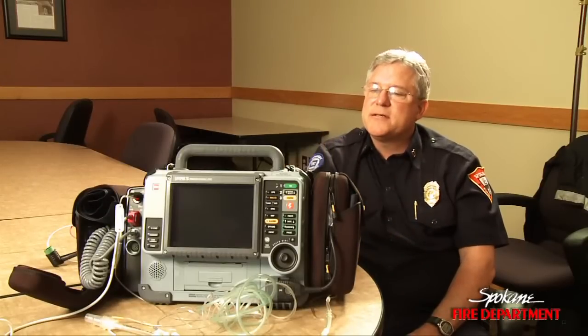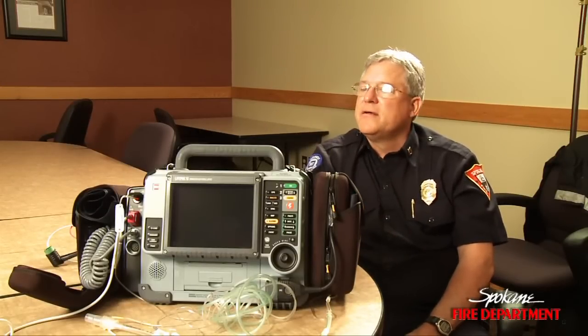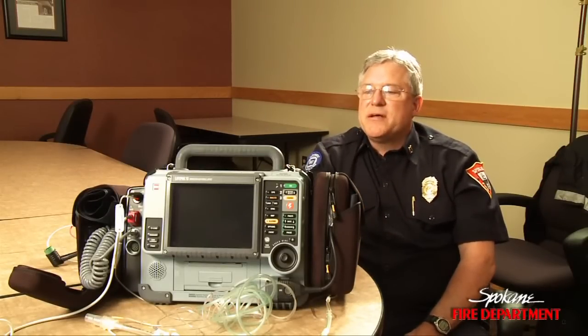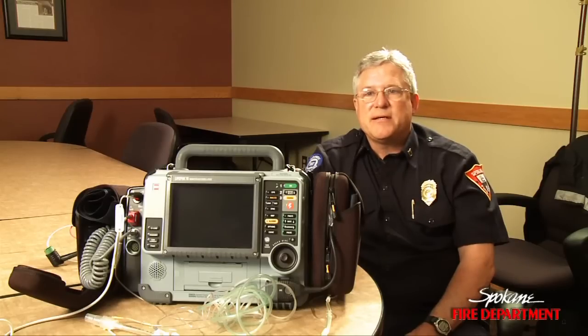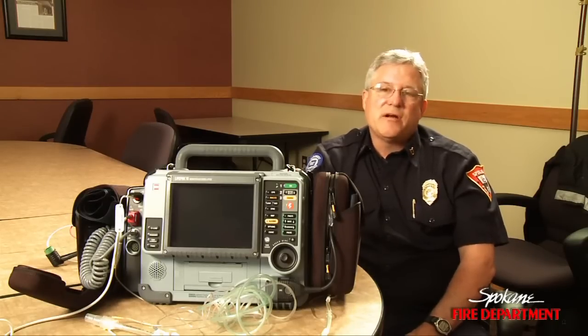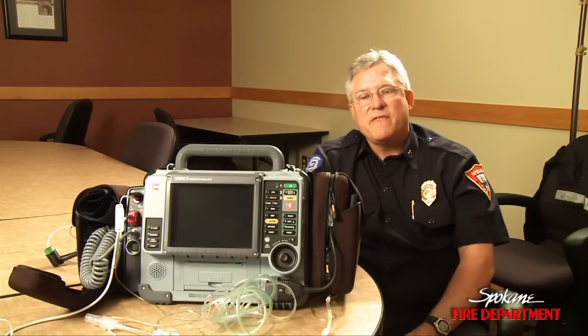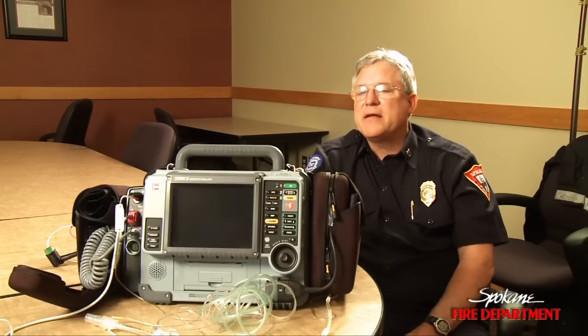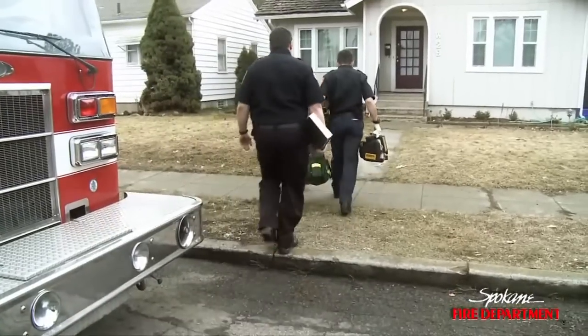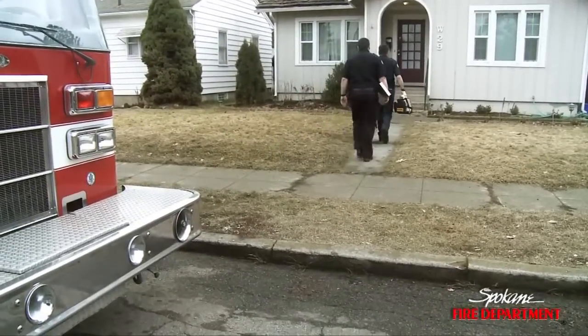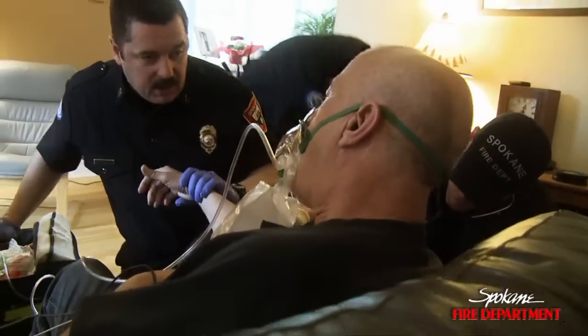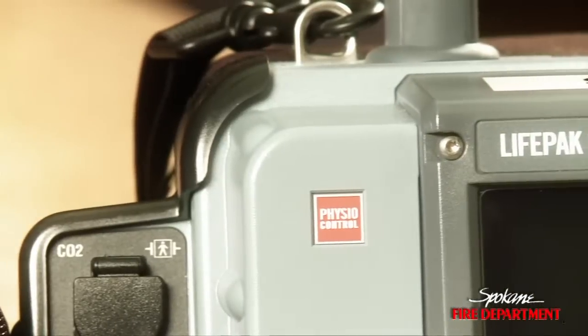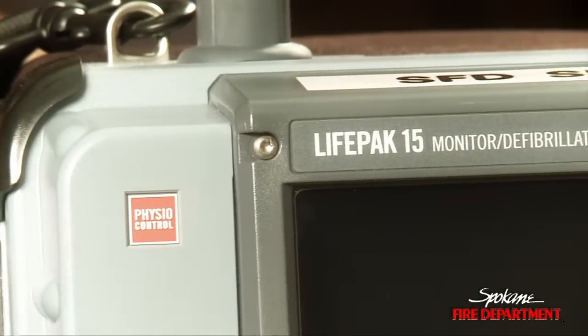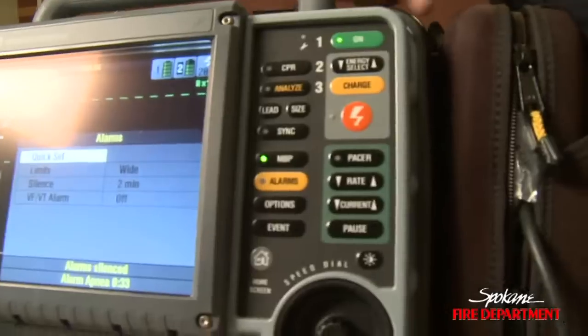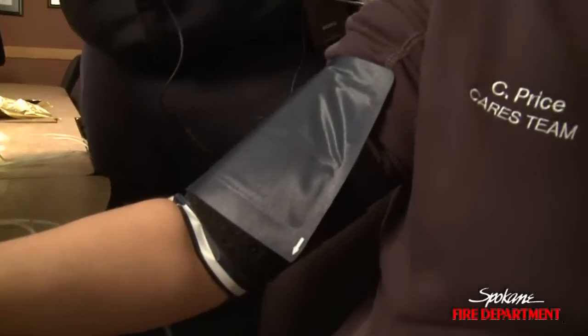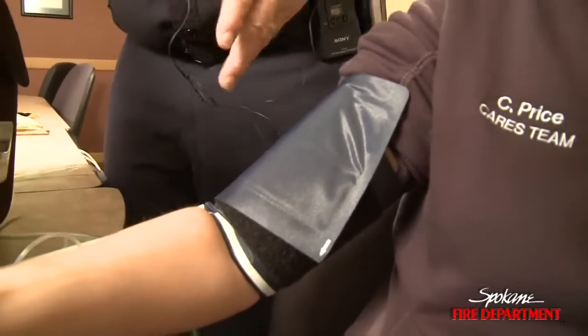Well, this is probably one of the best machines that we've had in a while. It replaced our old LifePak 12s. It's called the LifePak 15. And probably the two major components on it that are going to help us in the field is, one, it has a non-invasive blood pressure cuff. So we just put it on the patient, and we set it to either 2, 5, 10, or half an hour, and it takes blood pressures for us whenever we want it.